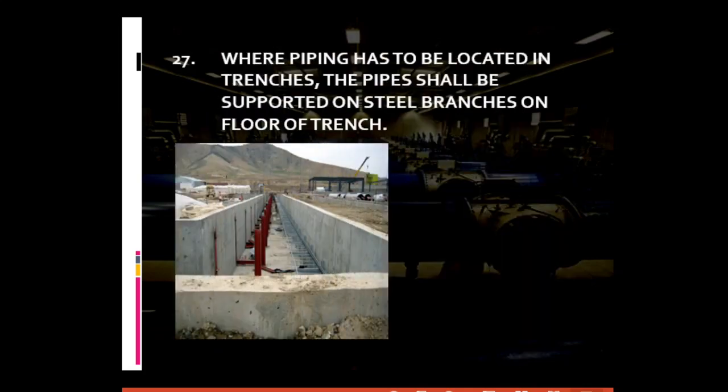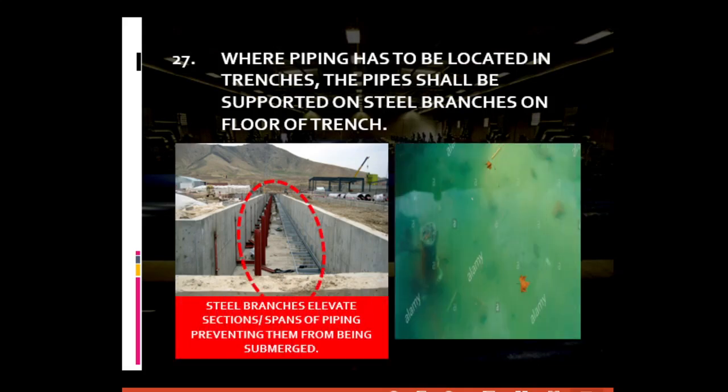For general piping requirement number twenty-seven: where piping has to be located in trenches, the pipes should be supported on steel branches on the floor of the trench. If piping is located in trenches or dug earth, they should be mounted on top of steel branches or supports to prevent them from being totally submerged, especially if such trench is accidentally flooded. This allows easier monitoring as well as easier access to the pipes. Steel branches elevate sections or spans of piping, preventing them from being submerged.